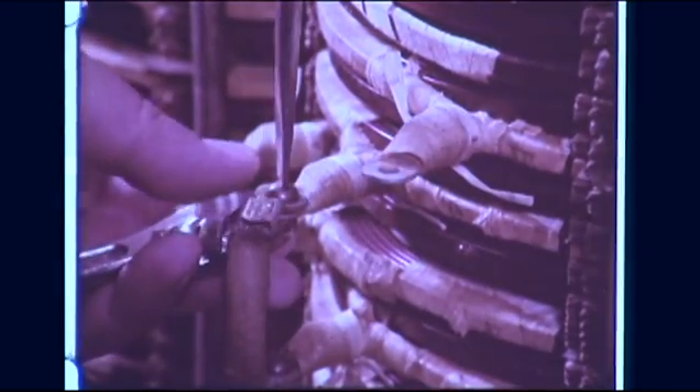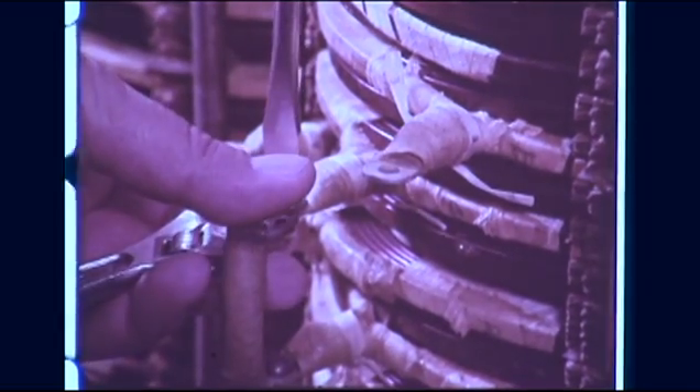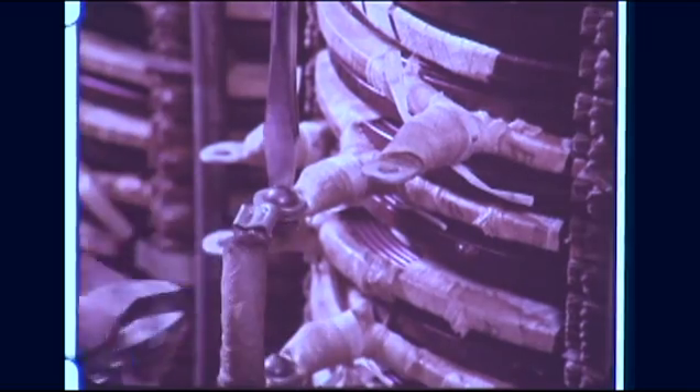In the next test, the four center sections of the outer coil are tapped out. This will tend to alter the force patterns in such a way that the upper portion of the coil will attempt to move upward, while the lower portion will attempt to move downward. On the second flash of the arrows, the short circuit will be applied. At a peak current of 180 times normal, the forces generated tended to split the coil from the center.